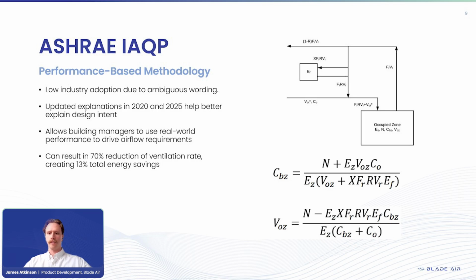So whether it's UV sterilization, HEPA filtration or electrostatic filtration, as I will mention a little later, we have more technology to clean the air. And now we have a standard that can actually take advantage of that to reduce the amount of fresh air coming in. Because this is always guaranteed with air quality monitoring, you can be sure that you're not reducing it to a point where it's going to create an unhealthy environment. This is always with the occupants in mind.